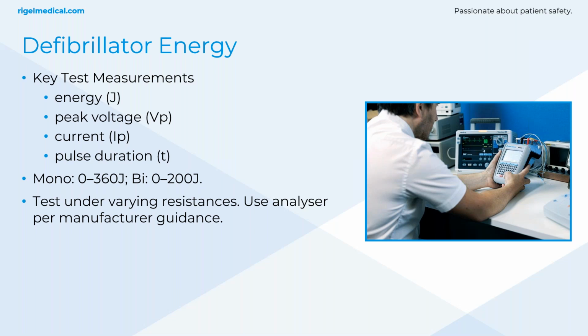And if you're using specific devices like, for example, our performance analyzer here, the Unipulse, it actually has a single screenshot grab of the energy that's delivered. So you will also see the waveform, and it gives you the pulse duration on screen. So effectively, it's a single shot oscilloscope to some extent. It gives you the full breakdown of what the waveform looks like, but also the values, which you can see if you scroll through the settings.